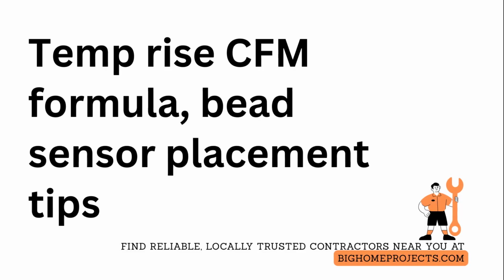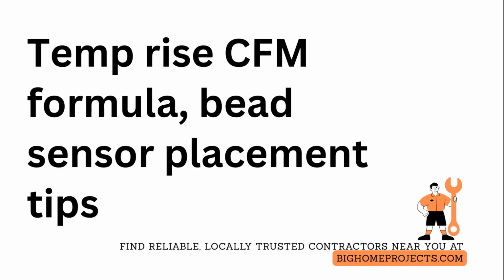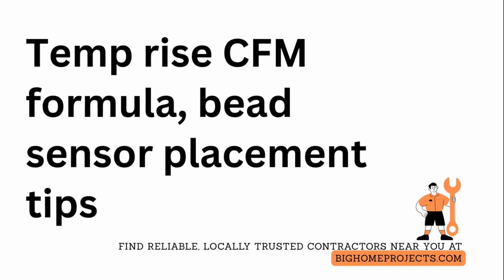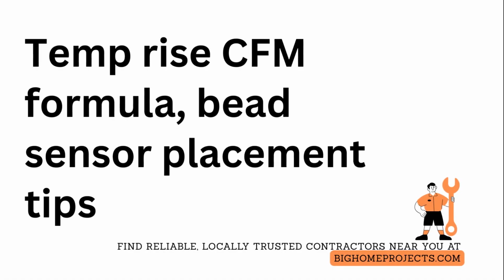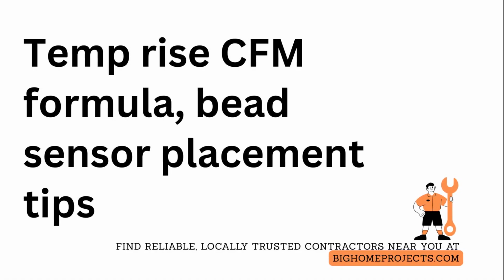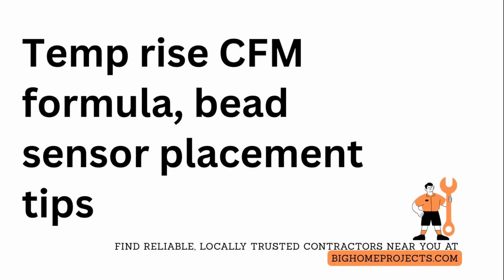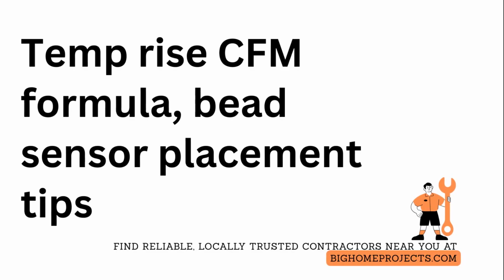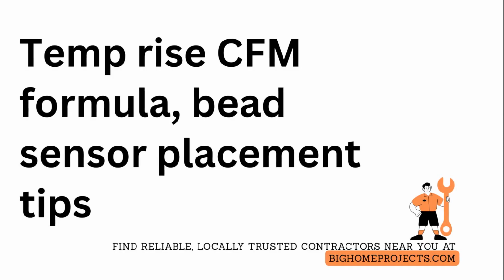Stop wasting time with bogus airflow readings. Use the heat capacity method with the heating, ventilation, and air conditioning temperature rise formula to calculate cubic feet per minute accurately by placing temperature sensors exactly where they belong in the ductwork.